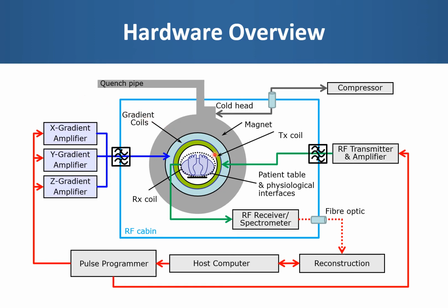Here is an overview of a typical superconducting MRI system. We start with the superconducting magnet here, which we are seeing in cross-section. The magnet contains windings of a special alloy of niobium and titanium, which when it is kept at the temperature of liquid helium, 4.2 Kelvin or minus 269 degrees Celsius, it becomes superconducting, which essentially means it has zero electrical resistance. When the service engineer first installs your magnet, he will inject several hundred amps into those windings, and that current will continue to circulate unimpeded because of the zero resistance until the magnet needs to be de-energized for some reason.